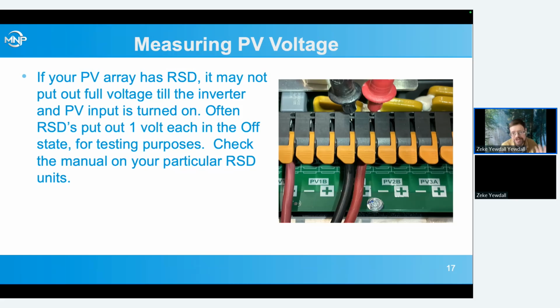If you have rapid shutdown on your PV array, remember you may not be measuring the full PV voltage. You often get 1 volt for each of the RSDs. So if you've got, say, 10 of them in a string, you'll measure 10 volts. Check the manual for your particular rapid shutdown system for how you test for proper output before it's activated.